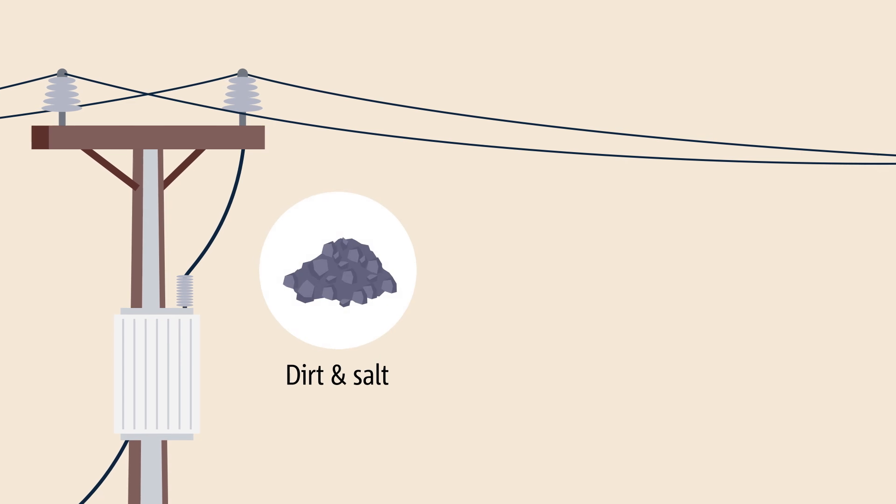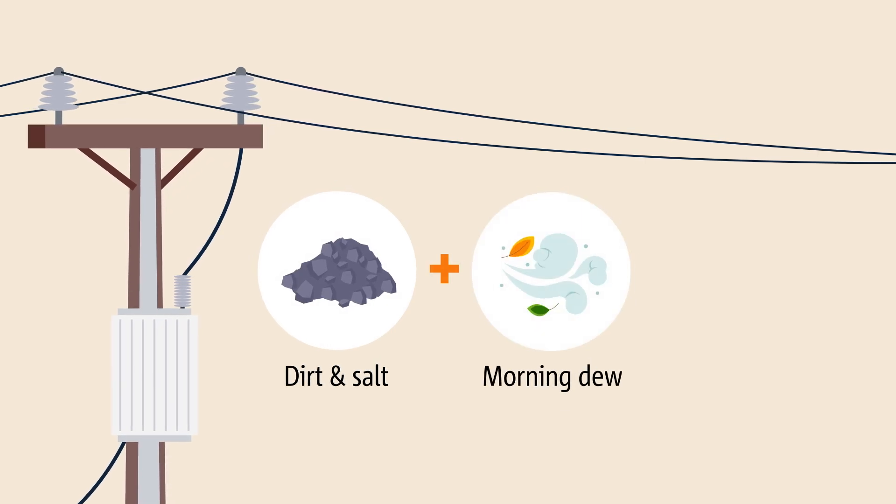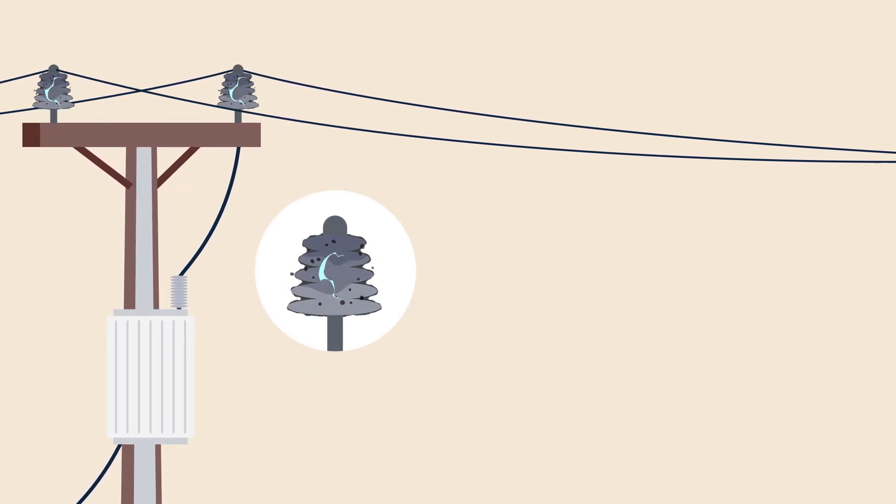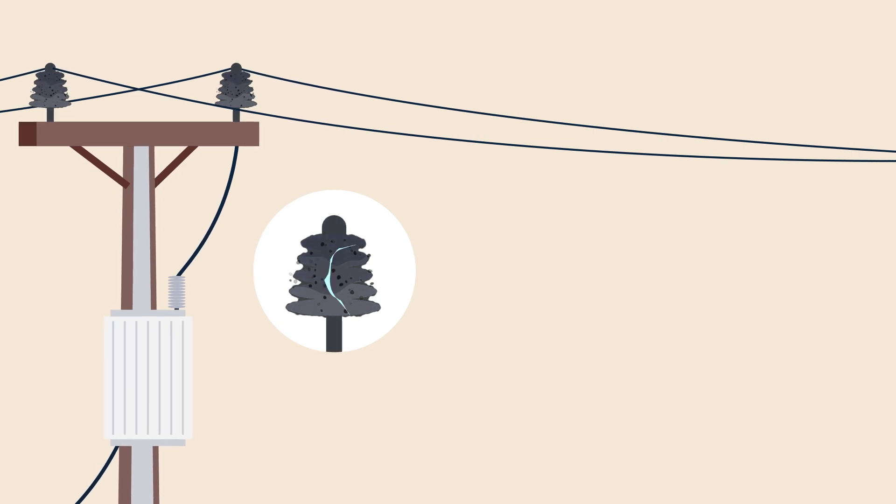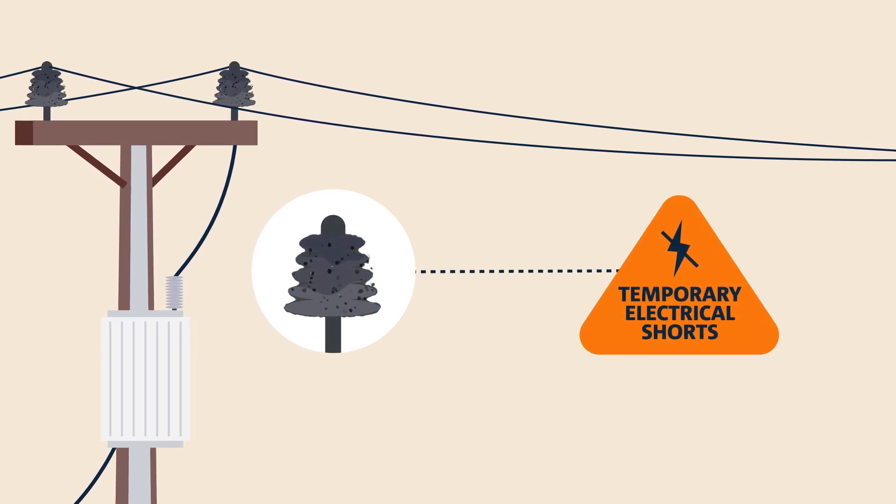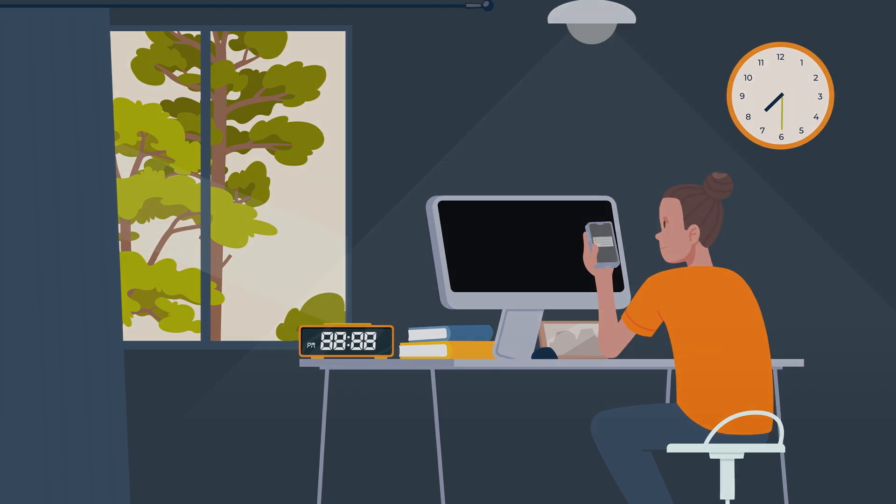This build-up of dirt and salt, combined with morning dew, mist or light rains, creates a conductive layer across the insulator's surface, which can lead to temporary electrical shorts, causing both temporary and prolonged power outages.